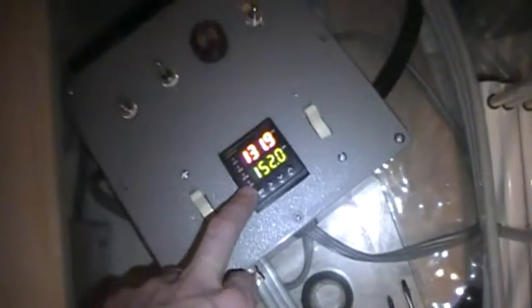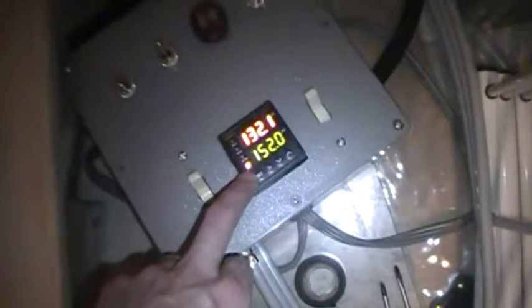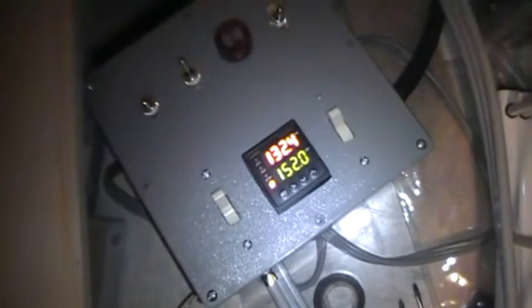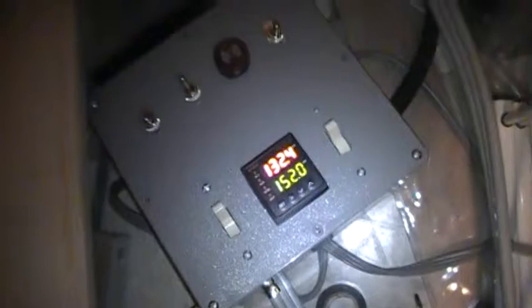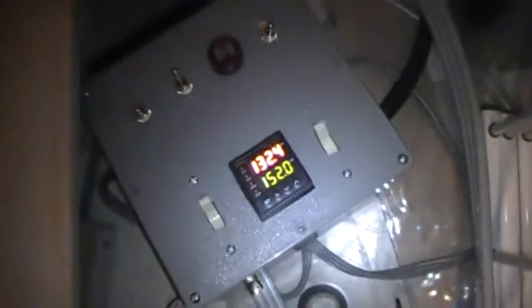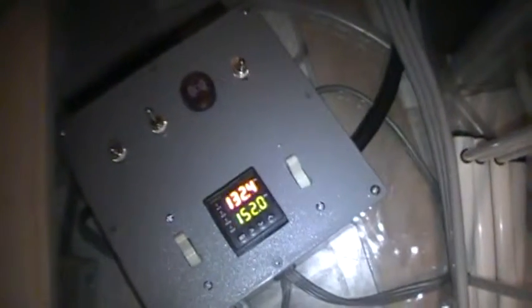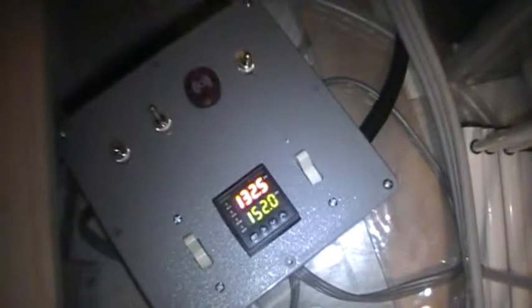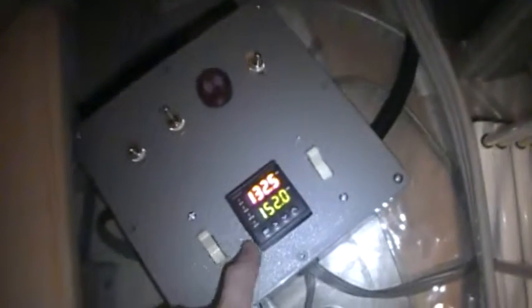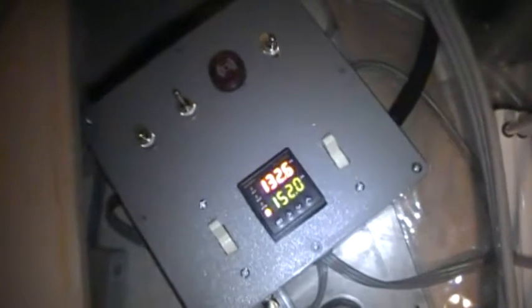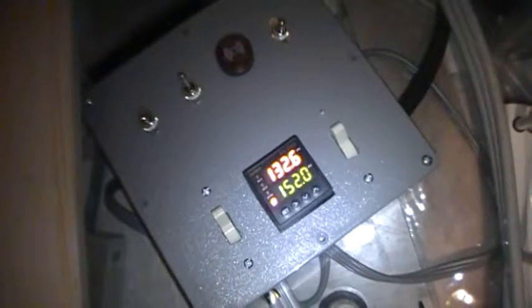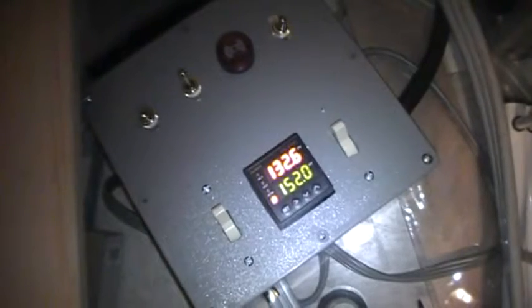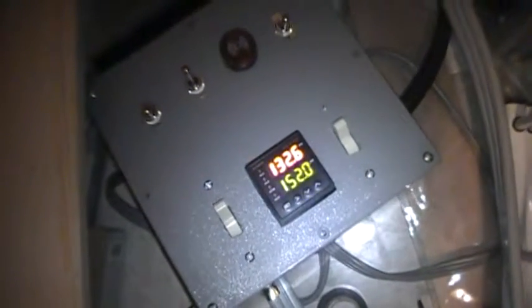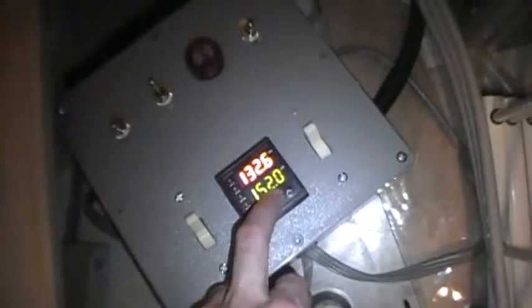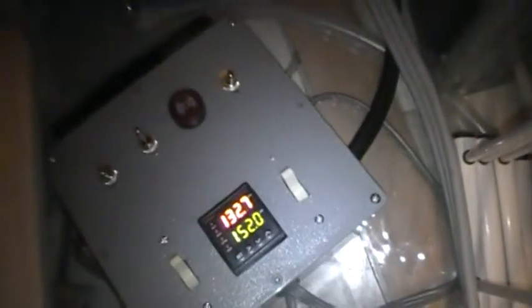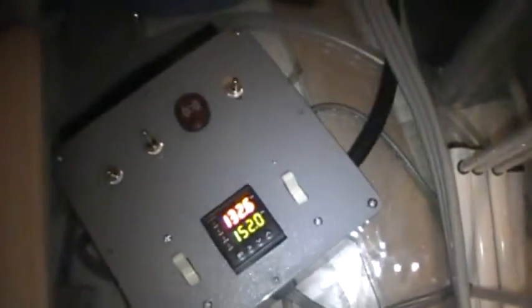Right now the PID is only giving intermittent power to that element. But as things continue, if it realizes it needs more power to get going, it'll start bumping up how long the element stays on instead of just short pulses. Once it gets close to the 152 we want, it'll realize we're getting close and need to slow down so we don't overshoot.